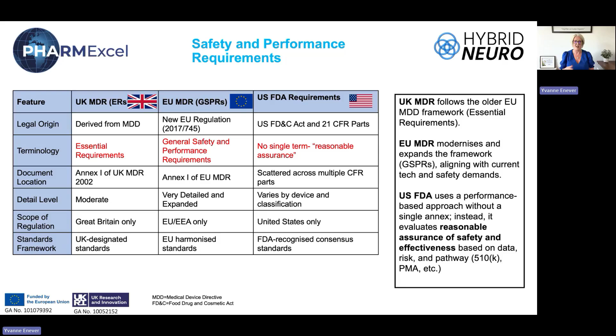In the US, they don't really refer to it as general safety and performance requirements, so there isn't a single term, but essentially they're asking you to provide reasonable assurance that your product is safe and it's going to be effective, and that's also dictated by the route that you take in the US. So you absolutely cannot sell any of your products in any of the markets unless you have demonstrated as a manufacturer that you have met all of those requirements. When I say it's a general checklist, actually there's a huge amount of work involved. All of this technical documentation that you're going to be gathering, when you are demonstrating how you are complying with each of those requirements, feeds into your quality management system and the technical documentation that's going to be reviewed by the authorities.